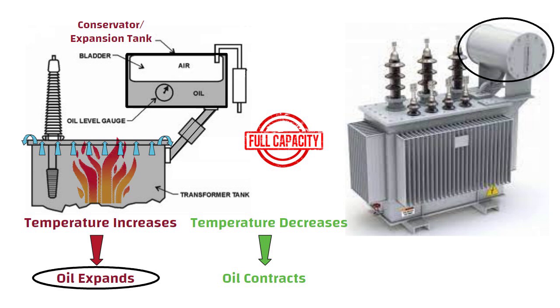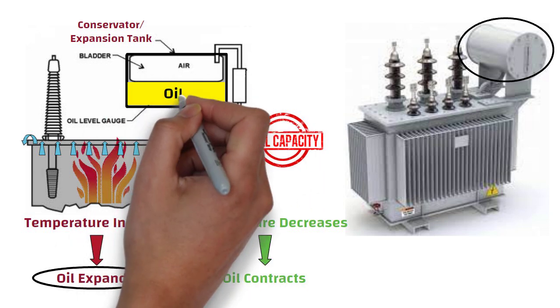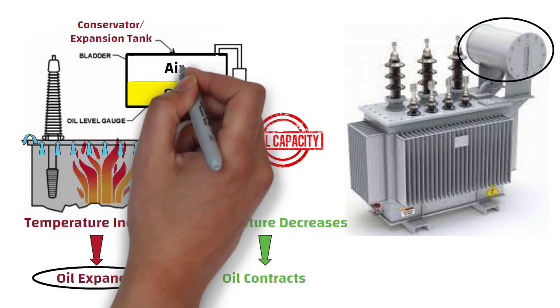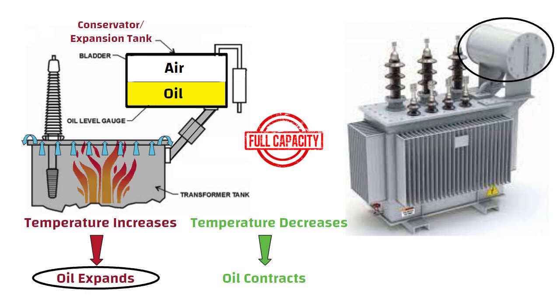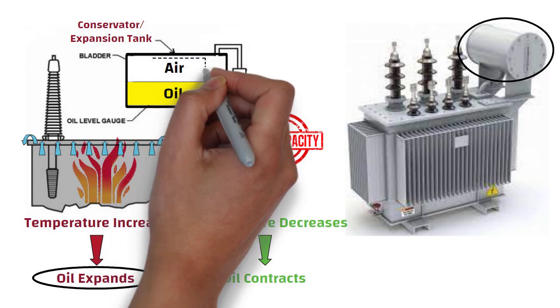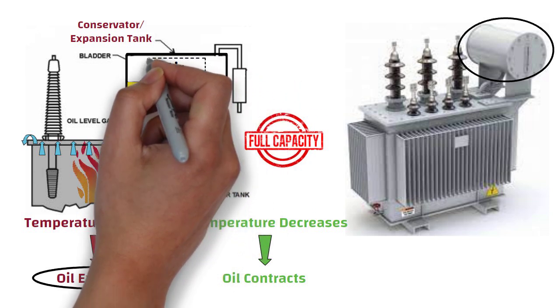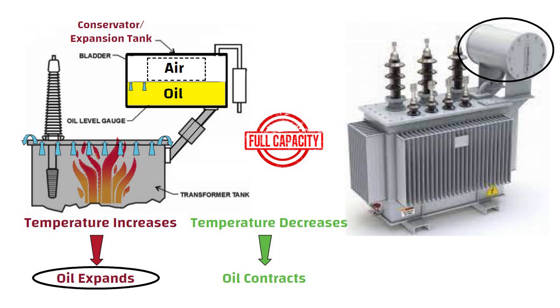This expansion tank is half filled with oil and half the portion is kept empty. The reason is, when oil expands, there should be some space available for the oil to be accommodated here. When the oil level comes up, the air will go out from the conservator tank.